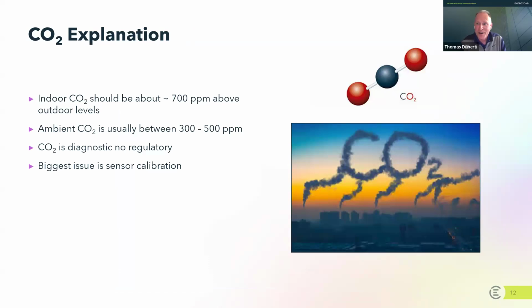Yet another variable that comes into play managing buildings, in addition to human comfort and humidity, is CO2. Let's talk about what's normal outside and blend back into building control. Ambient CO2 is typically between 300 and 500 parts per million. CO2 is everywhere, can't escape from it, and is typically used as a surrogate to understand air quality within buildings. Depending on whether you live in a rural area, urban area, near industry or away from industry, these values can change dramatically from place to place. On average, ambient CO2 is about 400 parts per million if you were to randomly go to a place in the country.